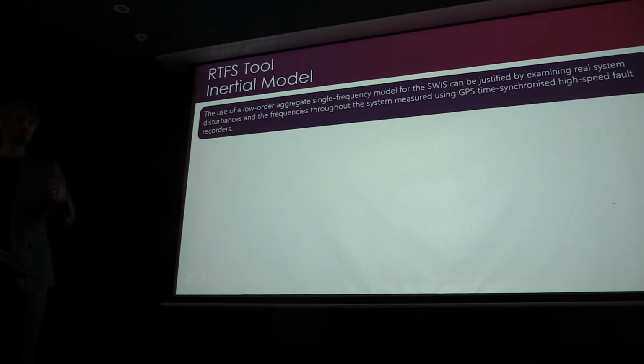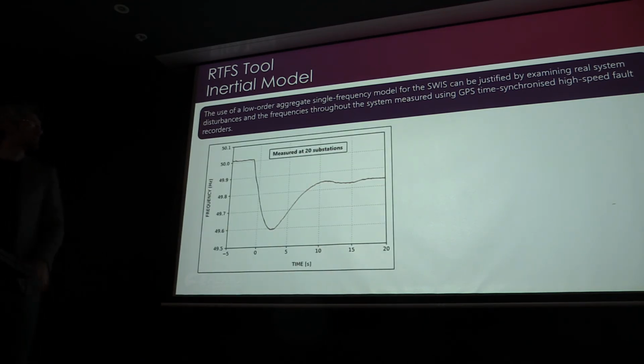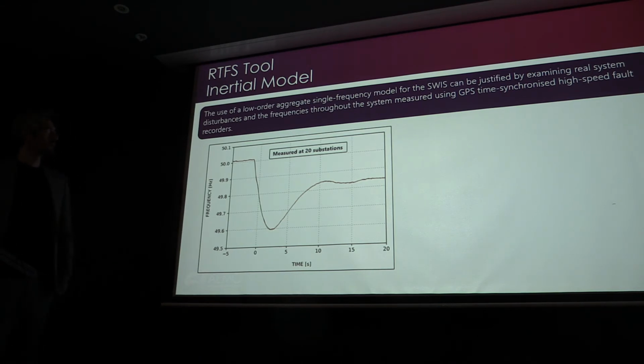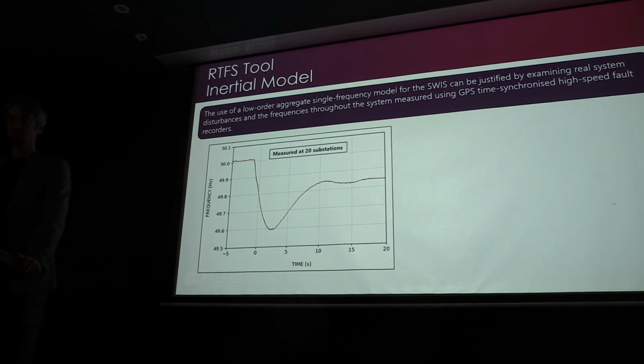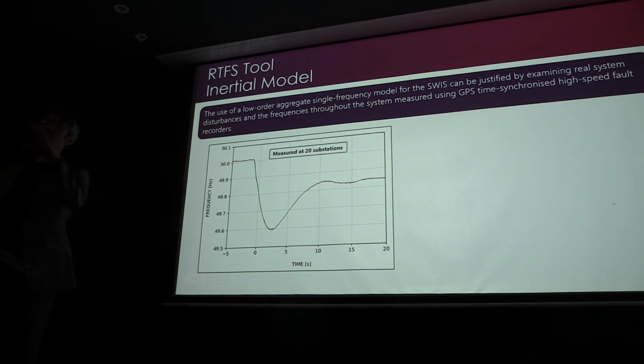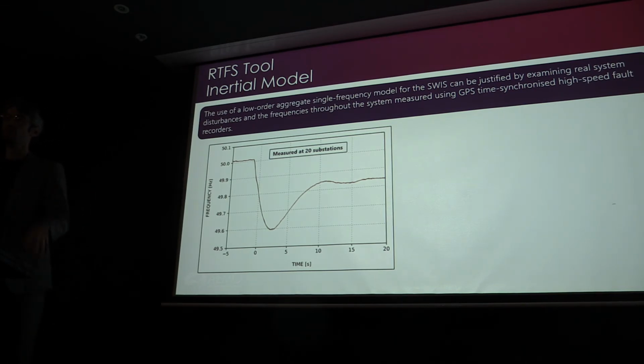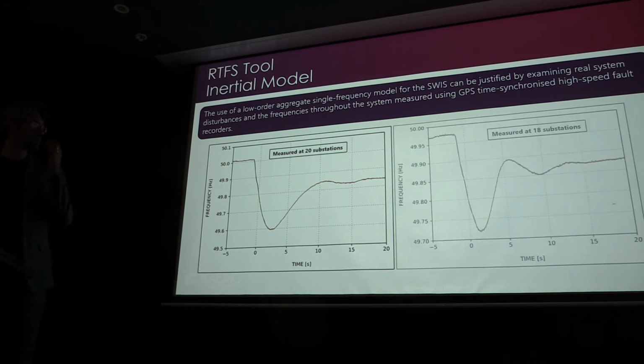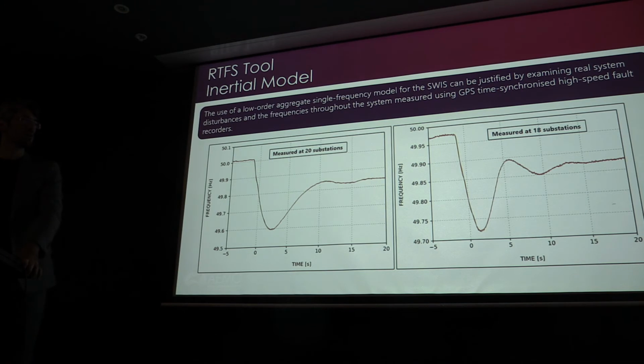So why do we use a single mass machine? Because of an actual event. We've got high speed data from different substations in SWIS. These are frequencies measured at 20 substations for this event. As you can see, not much difference. It means frequency is almost the same all over SWIS, so frequency is uniform across SWIS. And that's another event, where frequency is measured at 18 substations. Again, same concept. So that proves that using the single mass machine model is valid.